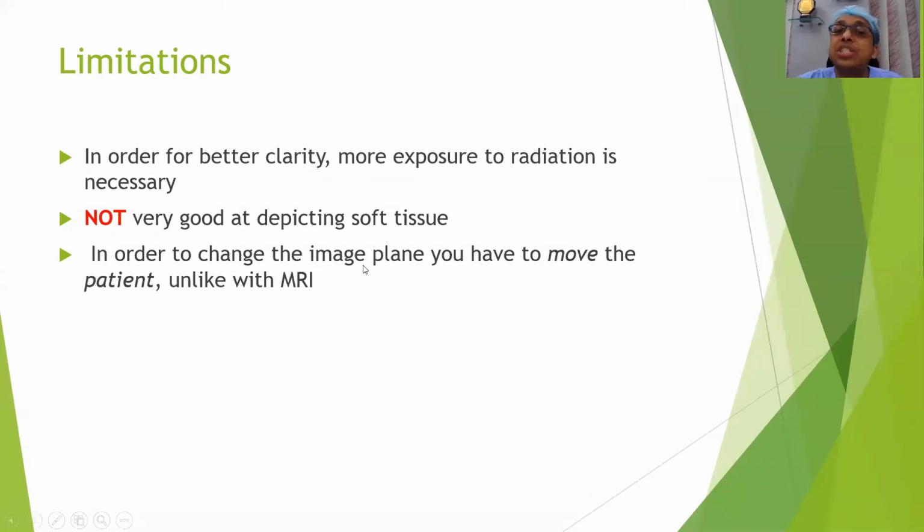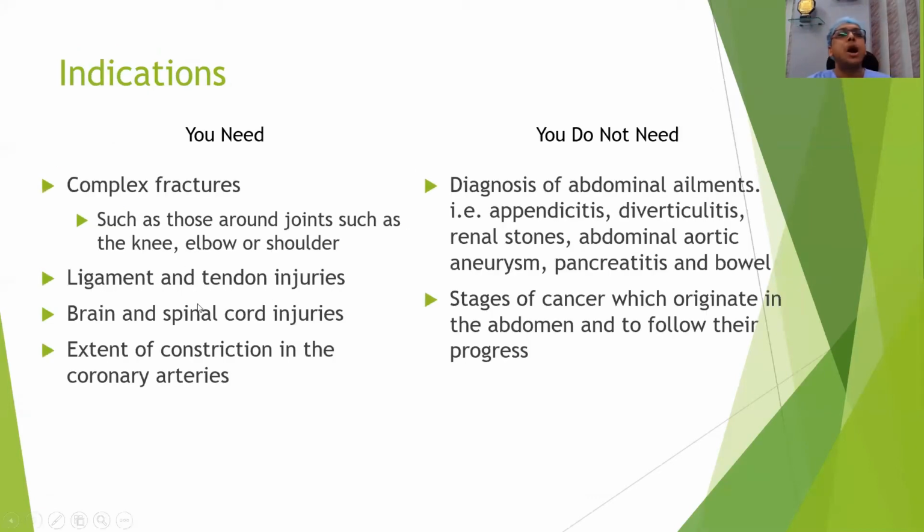In order to change the image plane, you have to move the patient, unlike with MRI. Essentially, the patient actually moves on the slider automatically. It's just a little bit of a hassle, but it's an automatic thing. I don't think it's a big deal or a huge limitation at all. It was there in the book, so I had it written down, but practically speaking, it should not be considered a limitation. All right, now indications.